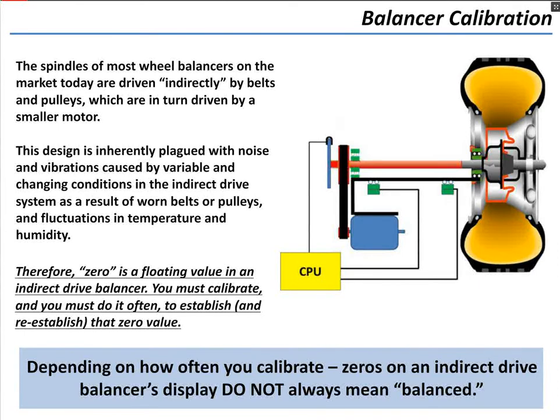And because of all this noise and the fact that this noise changes over time, zero, in other words balanced, is a floating value in an indirect drive balancer. And you have to calibrate, and you have to do it often to establish and reestablish that zero value. So with an indirect drive balancer, depending on how often you calibrate, zeros on the display don't always mean balanced. And that's a risk and a trap that a lot of folks aren't aware of. That zero is always based on what the current level of noise in the system is. And it's an artificial zero. So again, as things change, as you get belt wear, as your pulleys loosen up, as temperature warms up throughout the day in various climates, this becomes an issue, and you have to calibrate often.